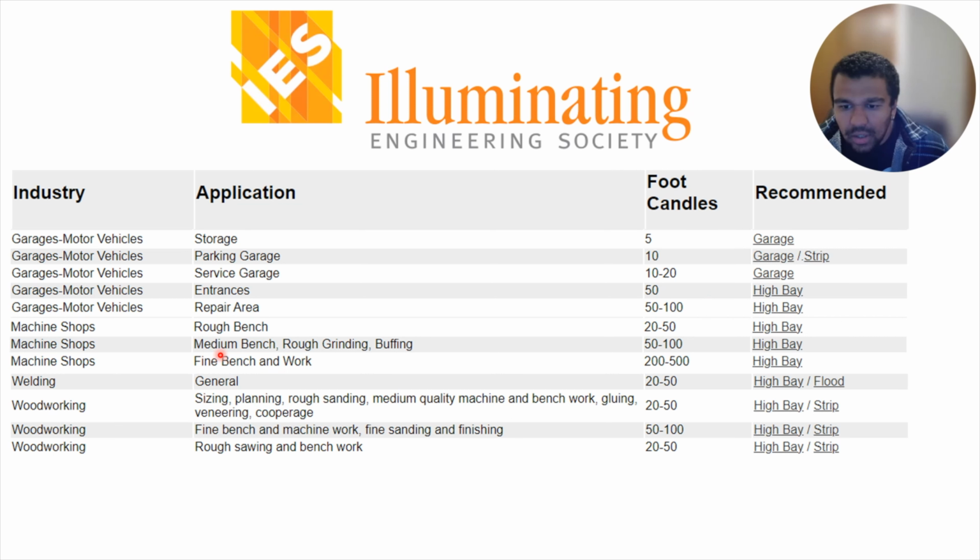Kind of same thing on machine shops. I was shooting for the medium bench, rough grinding, buffing. It's also 50 to 100 foot candles. And then in woodworking, fine bench and machine work, sanding, finishing, also in the 50 to 100.